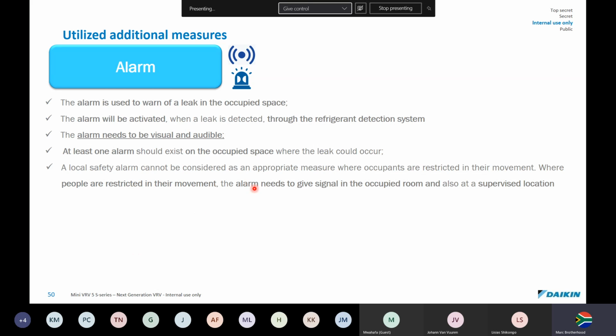A local safety alarm can't be considered an appropriate measure where occupants are restricted in their movements. Where people are restricted in their movement, the alarm needs to give the signal in that occupied room, and at a supervised location. So if you're living in hotel room number 4 and the leak is in your room, the alarm must go off in your room, as well as in a supervisor's or maintenance office. They must also get an alarm.